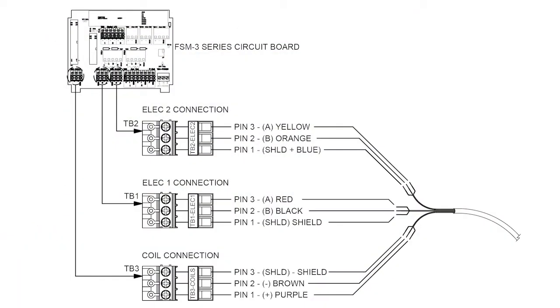Identify the flow sensor coil and electrode wires based on their wire lead colors. Terminate the wires in their pre-labeled terminal blocks as shown. Match the terminal block labels to the silkscreen text on the circuit board when repopulating the terminal blocks.